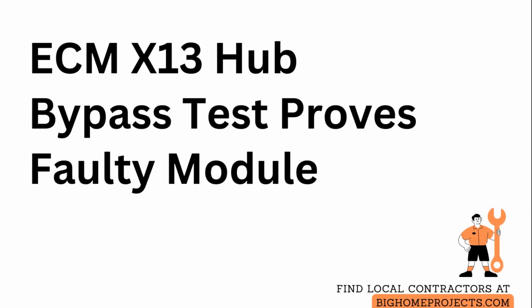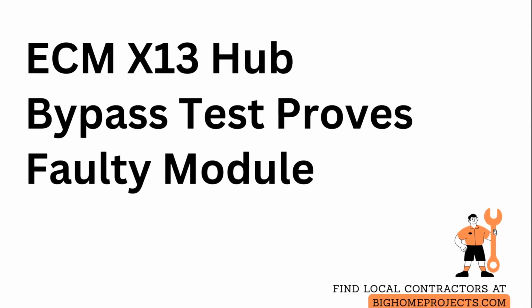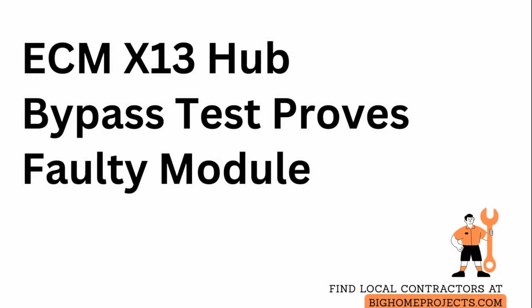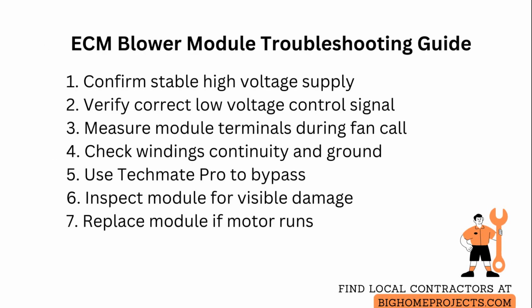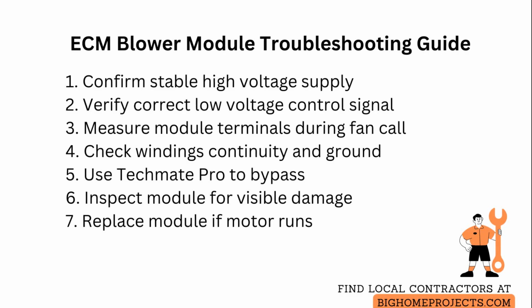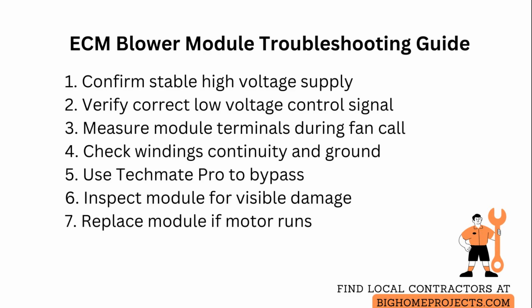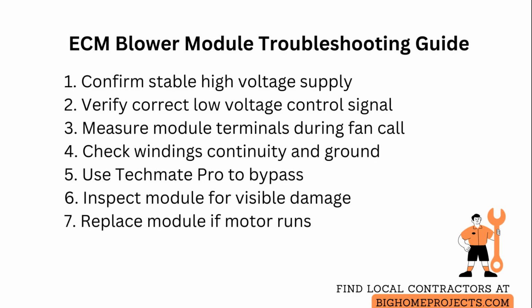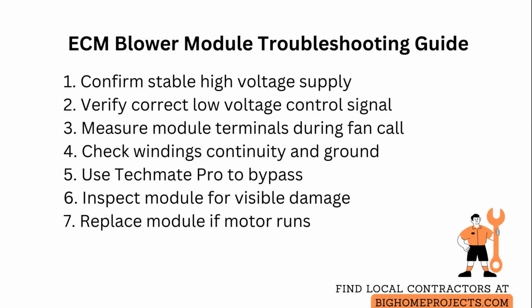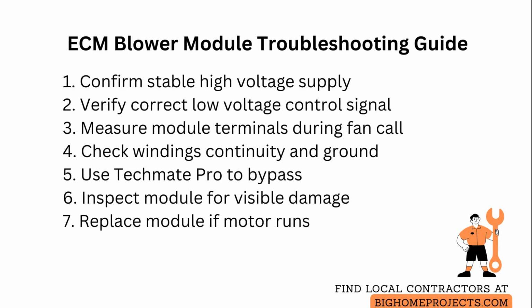Check the electronic control module or hub when an ECM blower shows intermittent operation or no spin at all. Start by confirming the blower motor is getting a stable high voltage supply at the module input, because fluctuating or missing mains will mimic module failure. Next, verify the correct low voltage control signal. For X13 and 2.3 modules, that is 24 volts AC, and for 3.0 modules, that is a direct current millivolt level. Measure at the module terminals, with the system calling for fan operation.